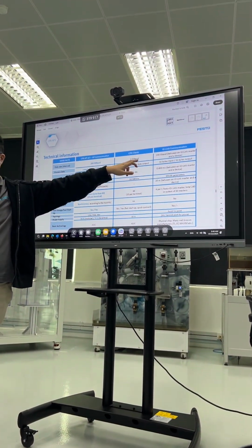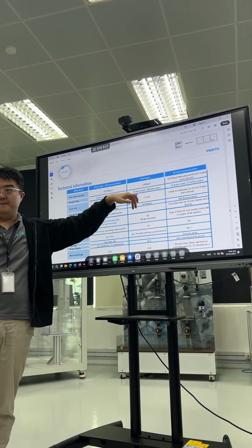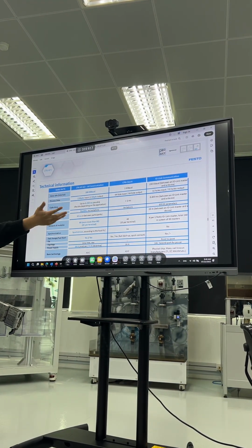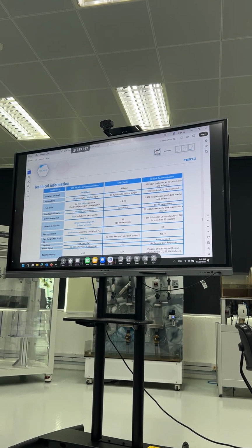It's also a Festo technology, but an older one. CBus has a data rate of only 1 Mbaud and a maximum process data of 64 bytes. Our new one uses AP communication, so the spec is a lot faster, with shorter cycle time and longer range between modules. So we can have more modules, and that's why we need to change from the old module to the new AP module.